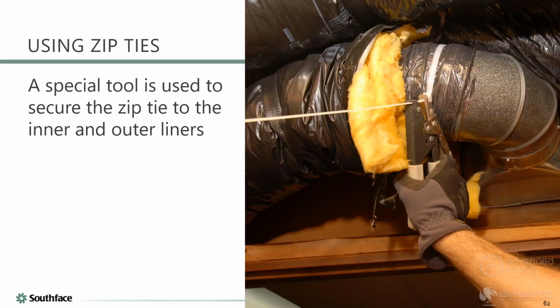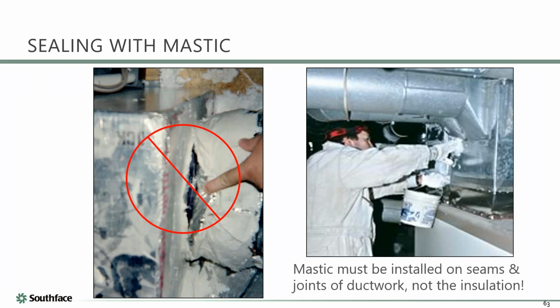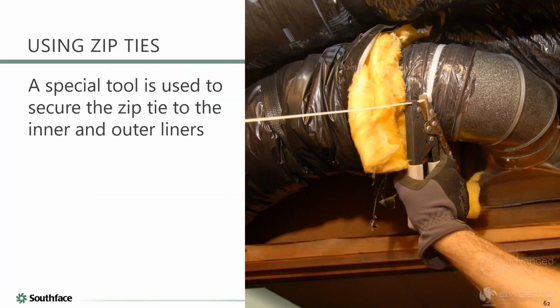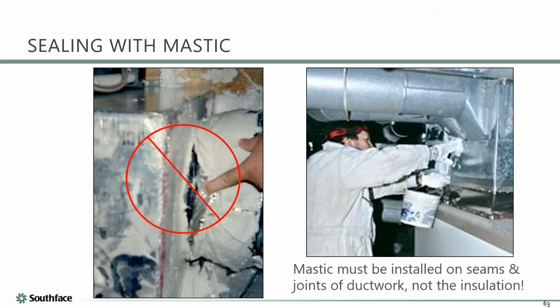And then there is actually a special crimping tool you would use to attach flex duct. I've done it with a pair of vice grips: you cinch it, disconnect it, reclip it and cinch it, and so on. So it can be done, but the tool is definitely the way to go. It's a lot easier and it'll cut off the excess when you're done. And there's a good example of that blacked duct that you were mentioning earlier. Oh yeah. I don't know where this duct is located, but if it's in an attic, don't do that. That's my advice. Okay, driving on.